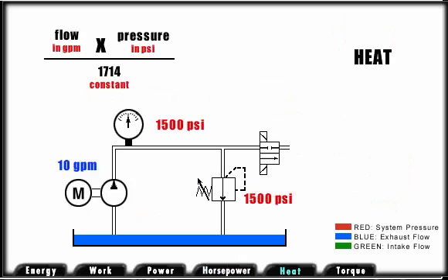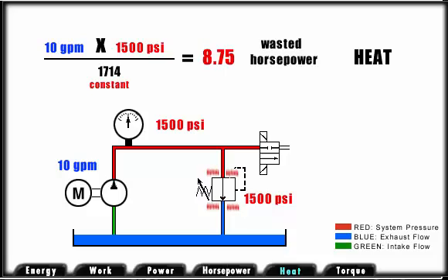The law of conservation of energy states that energy can neither be created nor destroyed, although it can change its form. Energy in a hydraulic system that is not used for work takes the form of heat. For example, if we have 10 gallons per minute going through a relief valve which has a pressure setting of 1,500 psi, we can calculate the energy being converted to heat.